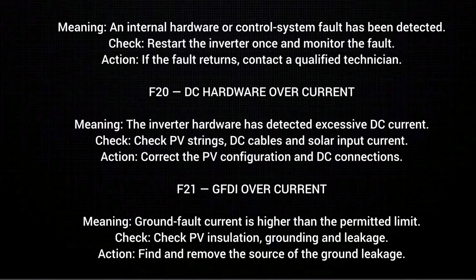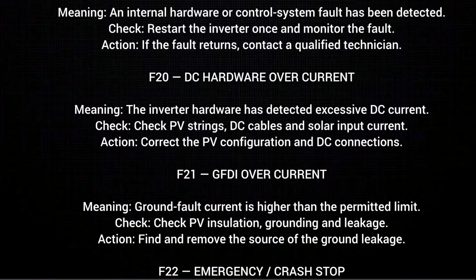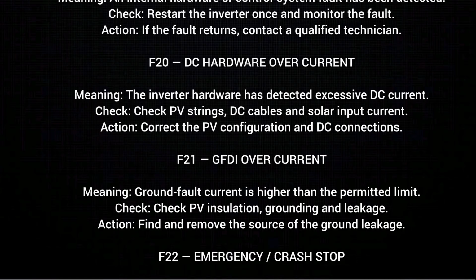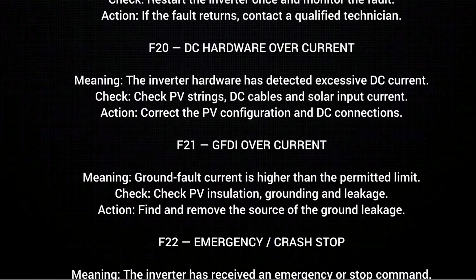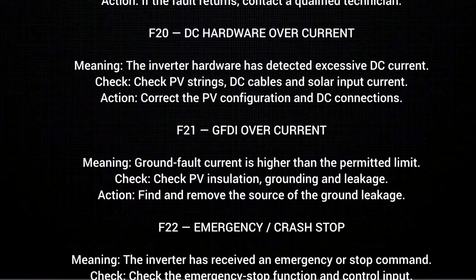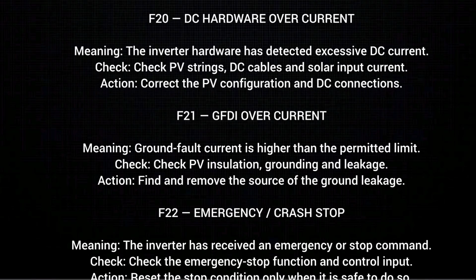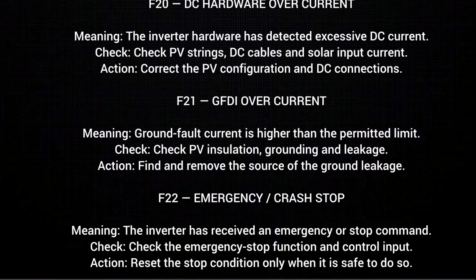F20 DC hardware overcurrent, meaning the inverter hardware has detected excessive DC current. Check. Check PV string, DC cables and solar input current. Action. Correct the PV configuration and DC connections.